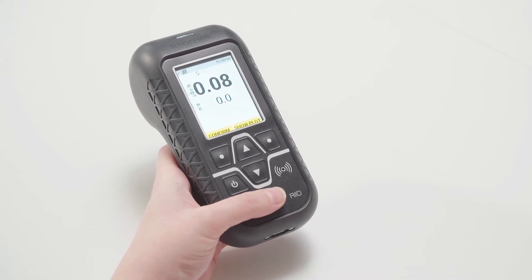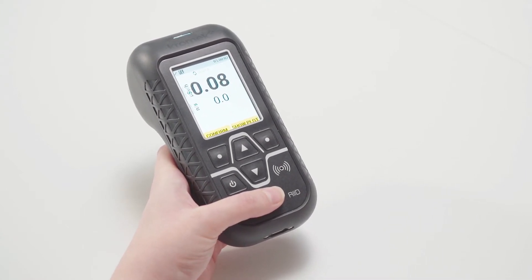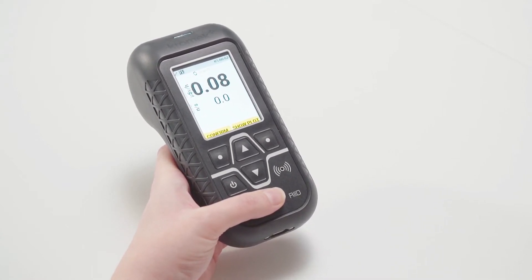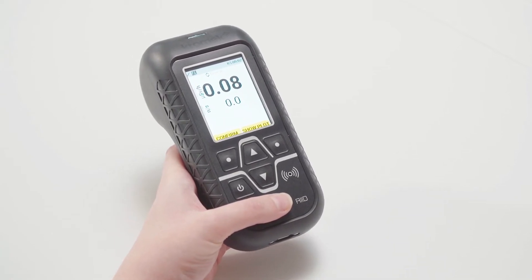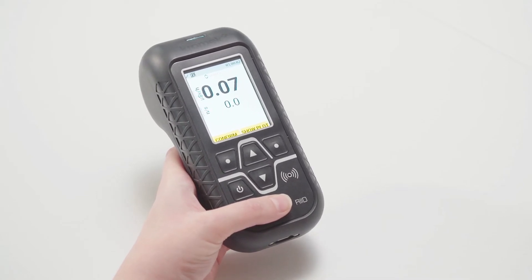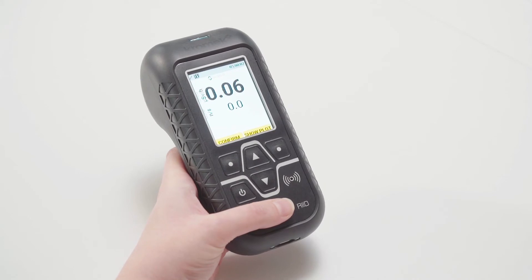This is the D5 RIID. It houses a CLLBC detector, which offers 3.5% resolution on all spectral data. It's really small and lightweight enough to allow easy one-handed operation, with the ability to easily access all buttons and controls, even while wearing PPE.